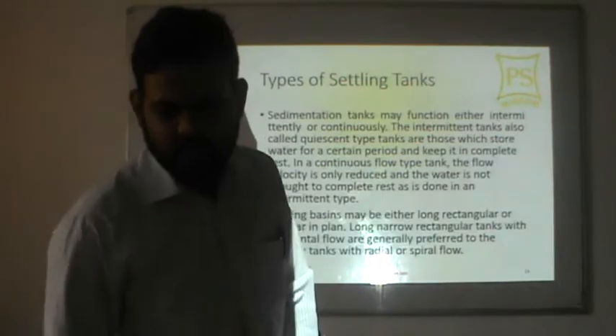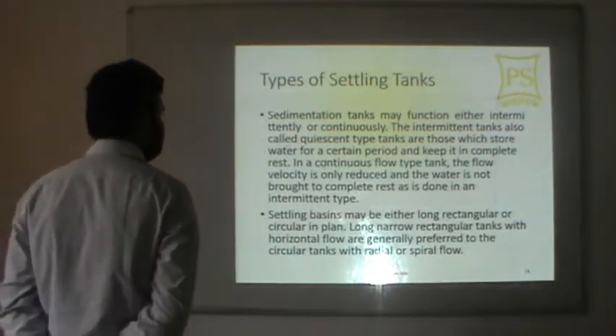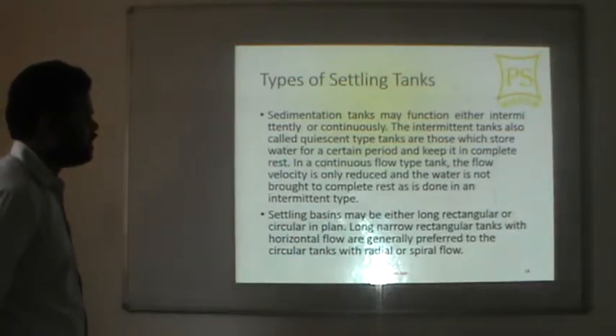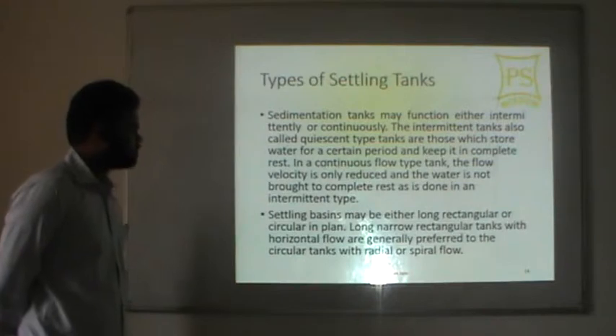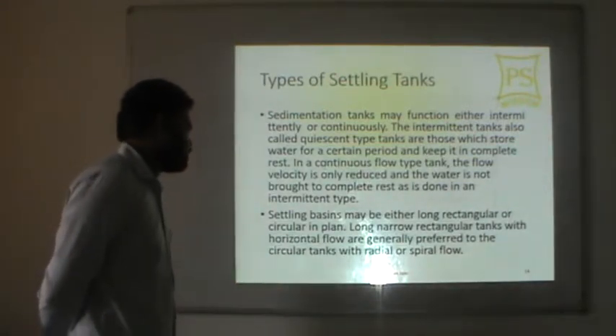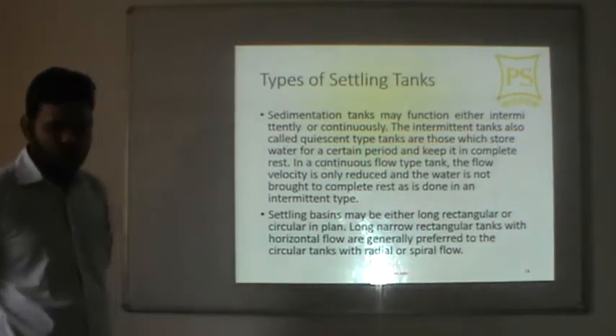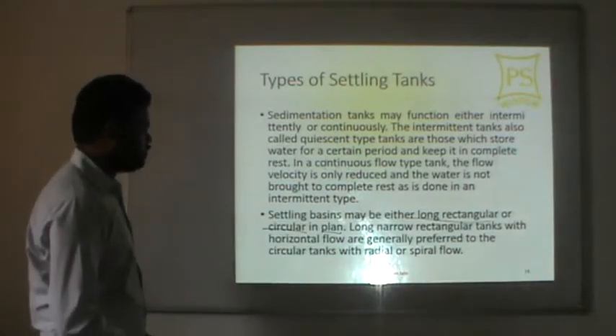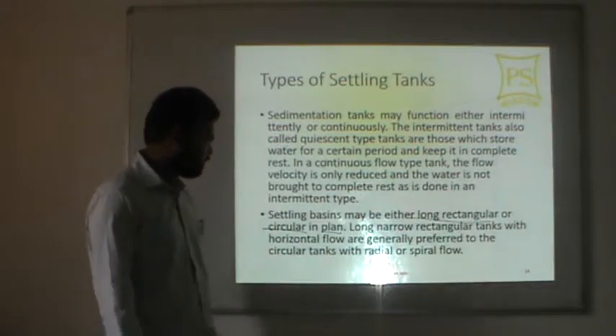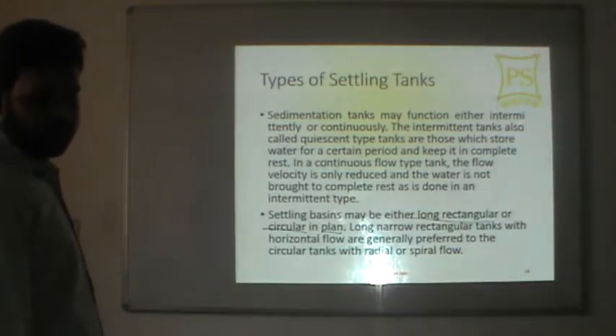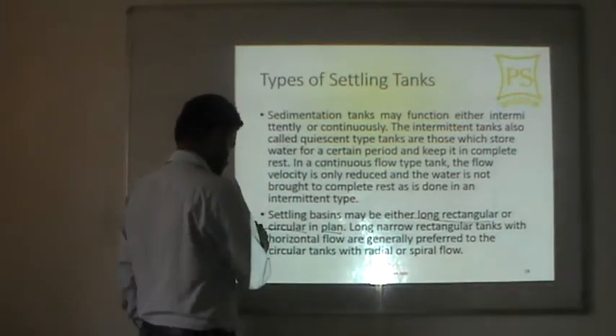Types of sedimentation or settling basins: a sedimentation tank may function either intermittently or continuously. Intermittent types, also called fill-and-draw tanks, store water for a certain period and keep it in complete rest. In continuous flow type, the flow velocity is only reduced. Settling basins may be either long rectangular or circular in plan. Long narrow rectangular tanks have horizontal flow, while circular tanks have radial or spiral flow.